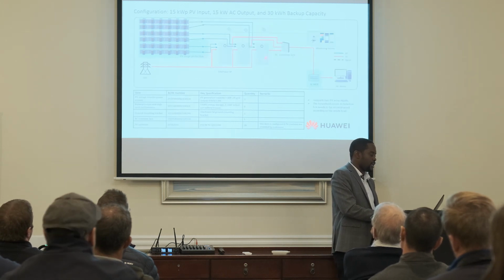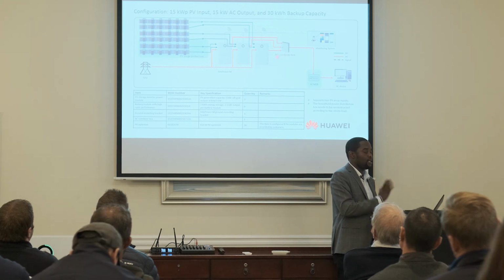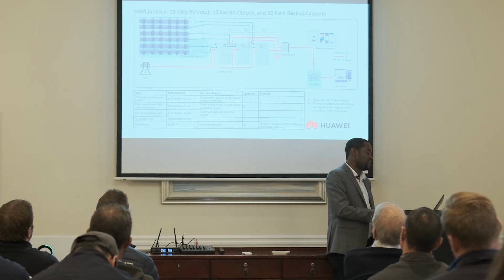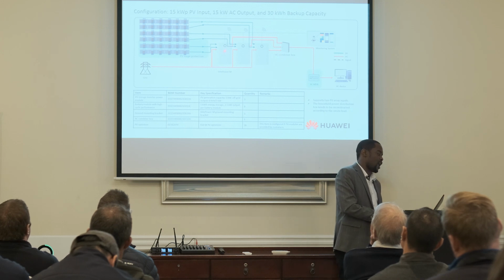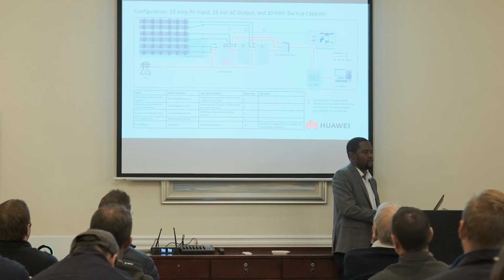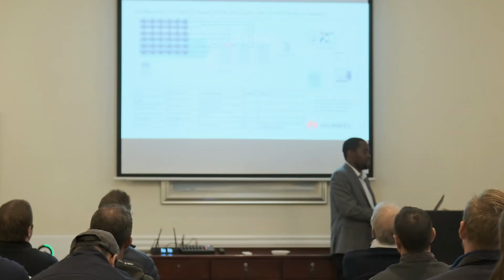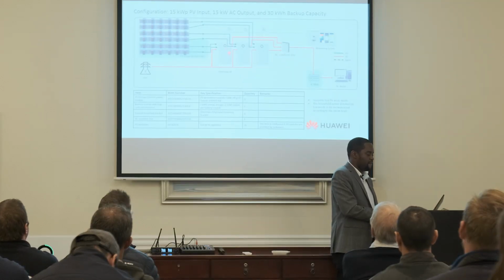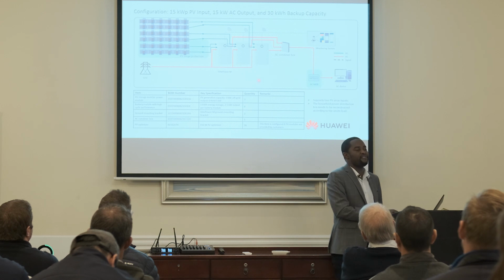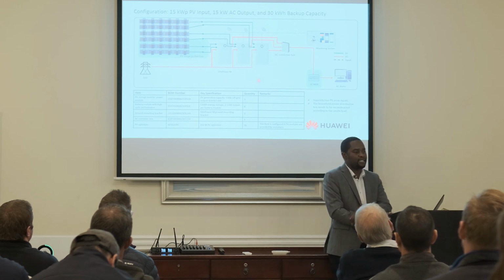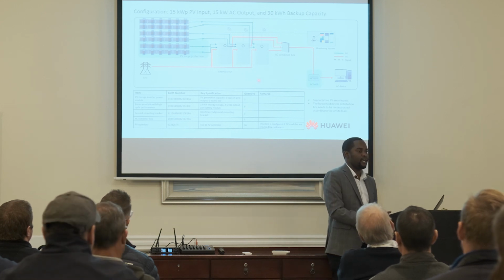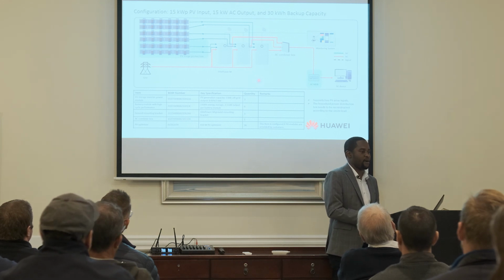If you're in parallel, you can have 3 inverters currently in one phase, in single phase configuration, but very soon, maybe after a month or so, we should be able to put one inverter on its own phase. Then we have a combined 3-phase output, right? So this is a massive battery bank that you can build. Can you imagine we've got this system and we have got 6 of these, so you can actually have a 90 kilowatt hour battery bank and a 15 kilowatt inverter power, right?